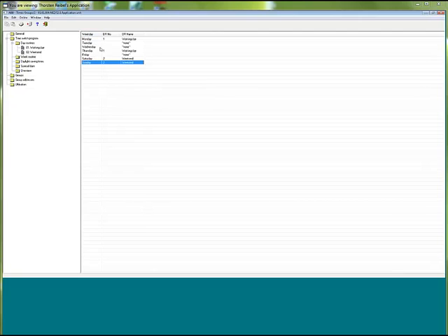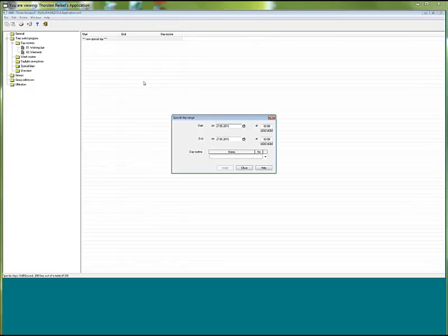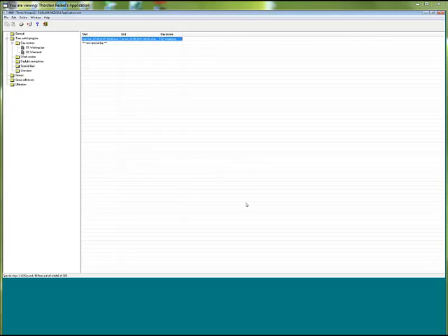Okay, now every Monday, every Tuesday happens the same because these are our routines we have assigned. To overcome the situation, we can create special days. Yeah, for example, here, special day. What does it mean? Not only special day, but special period, you can say. I click twice on this, and now you can adjust here a period, whatever you want, from today until June, whatever you would like to have weekend program, because this is like holiday for you. And now at that time, it's different from the normal week routine. Only the weekend program runs. Very simple to create any special periods or days.